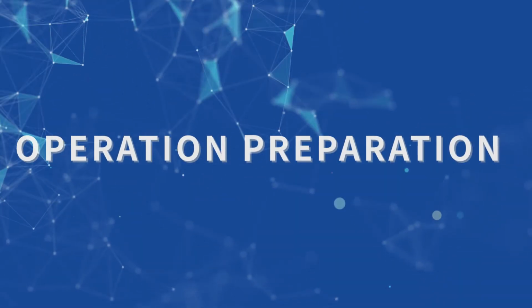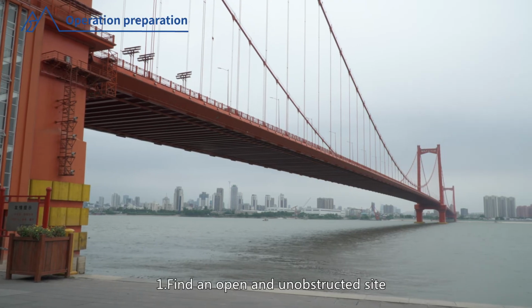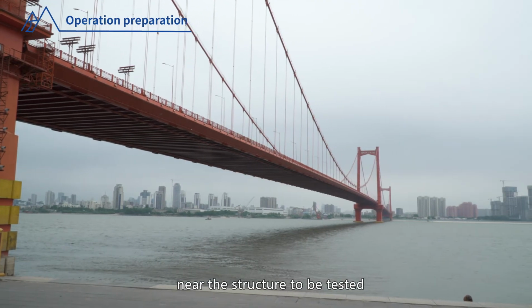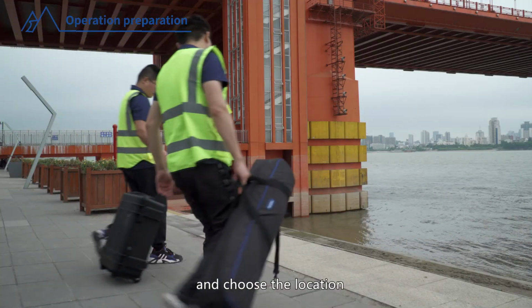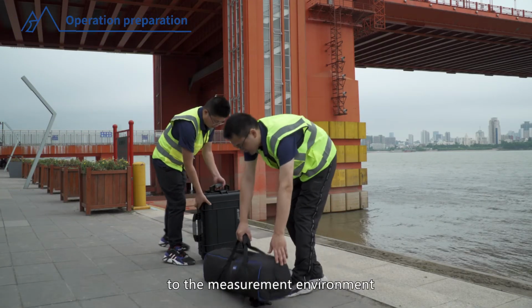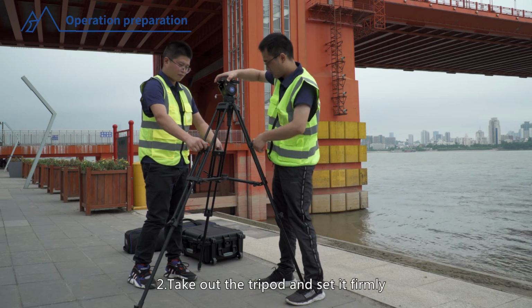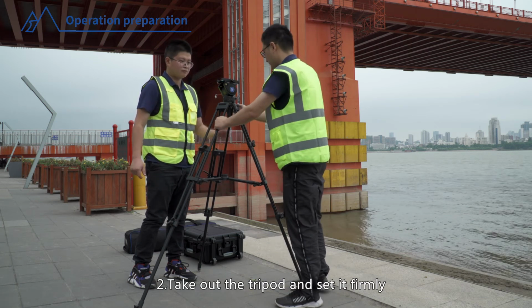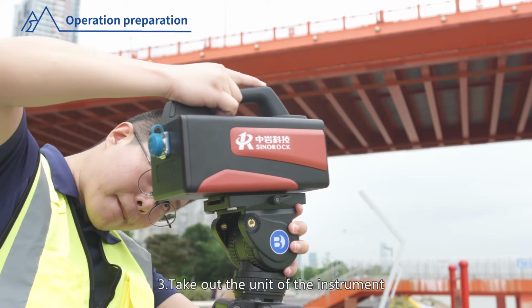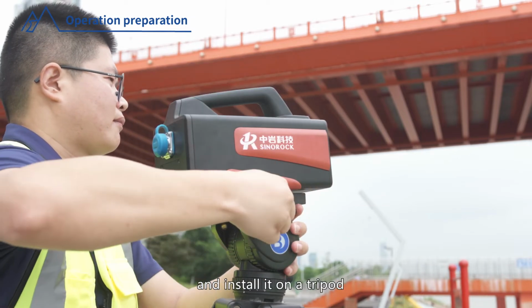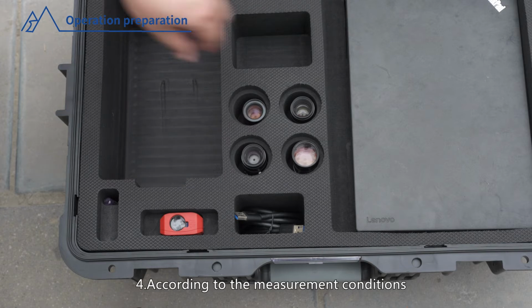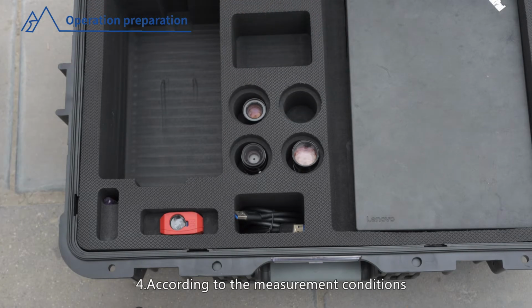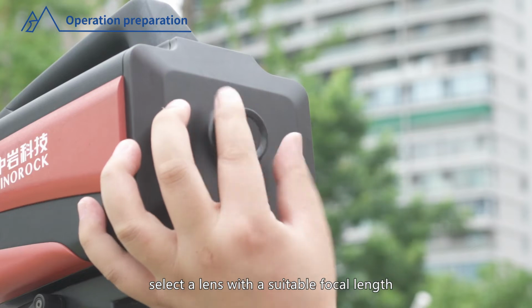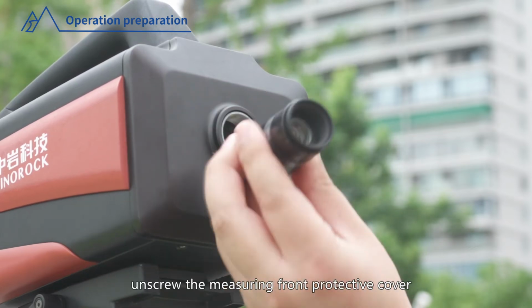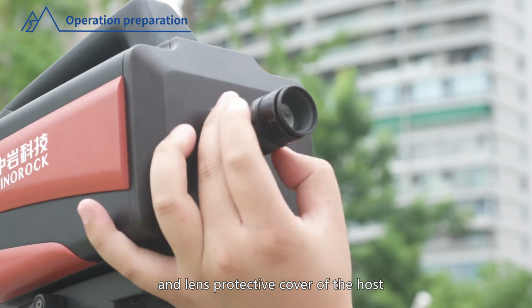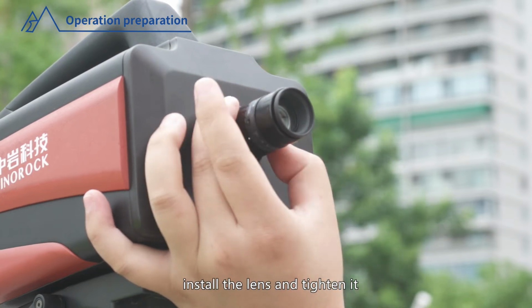3. Operation Preparation. 1. Find an open and unobstructed site near the structure to be tested, and choose the location of the instrument according to the measurement environment of the structure. 2. Take out the tripod and set it firmly in the selected position. 3. Take out the unit of the instrument and install it on the tripod. 4. According to the measurement conditions, select a lens with a suitable focal length. Unscrew the measuring front protective cover and lens protective cover of the host. Install the lens and tighten it.